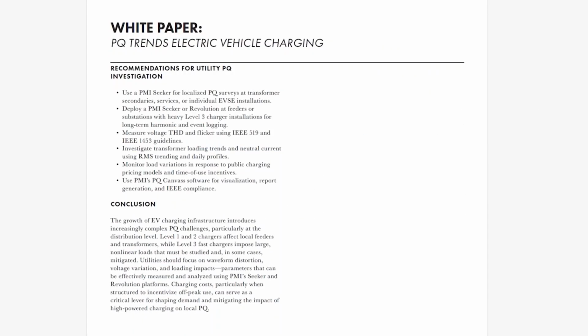Good question. What would be the solution for harmonics and sags? So that's a big question. The solution for harmonic distortion usually is based on who's in violation of what standard. If the charging system is exceeding their allowable current injection per IEEE 519, generally that would involve harmonic filtering on the customer side, the tuned filters that block certain harmonics or active filtering systems.